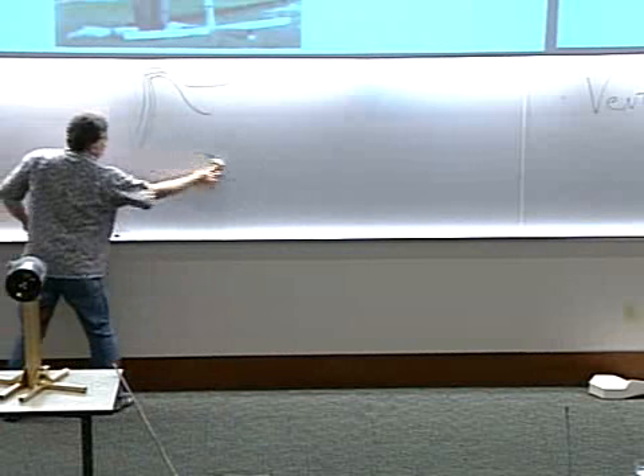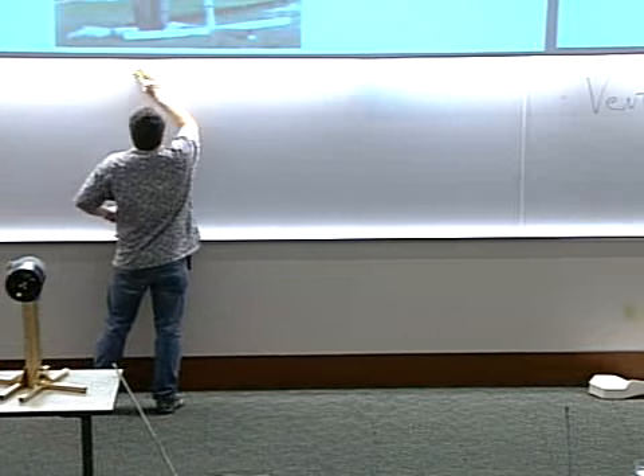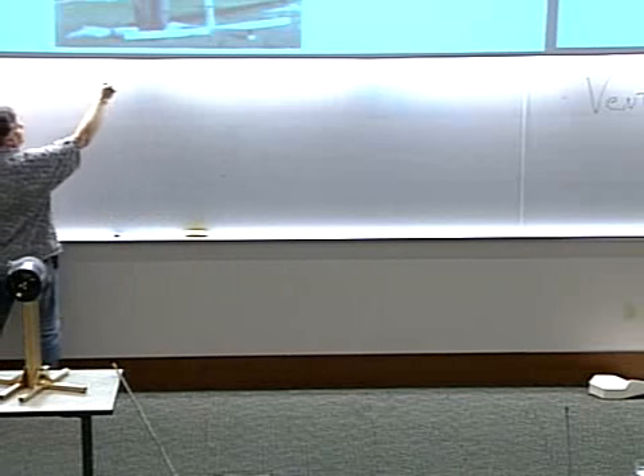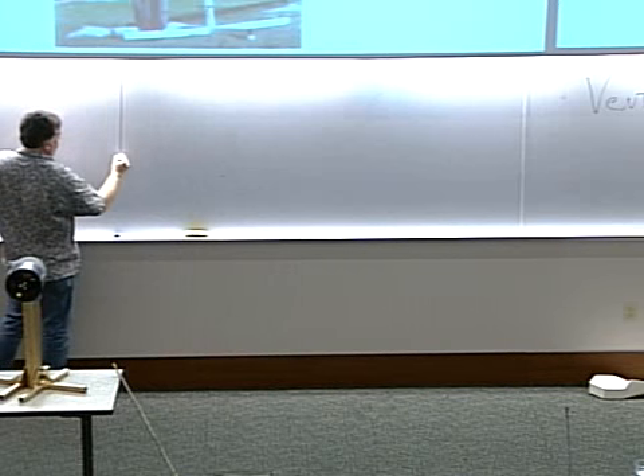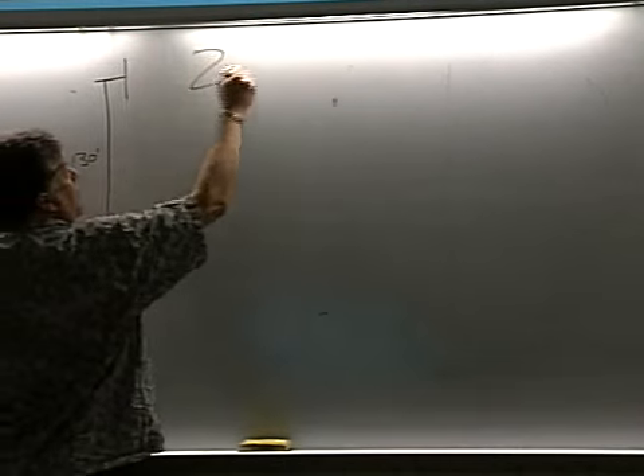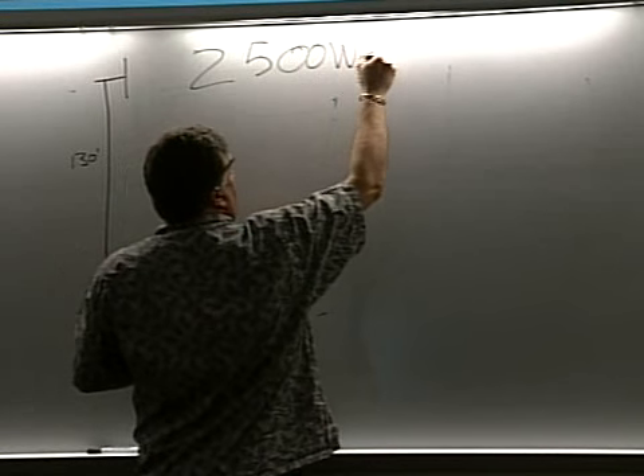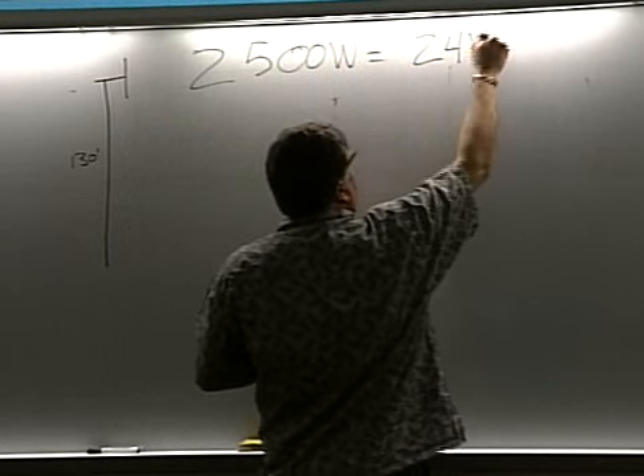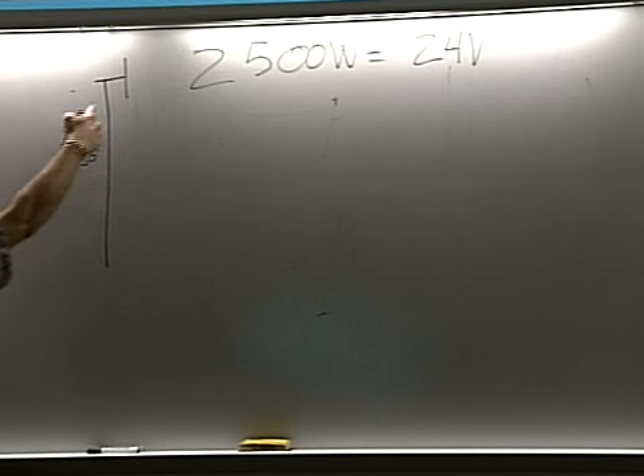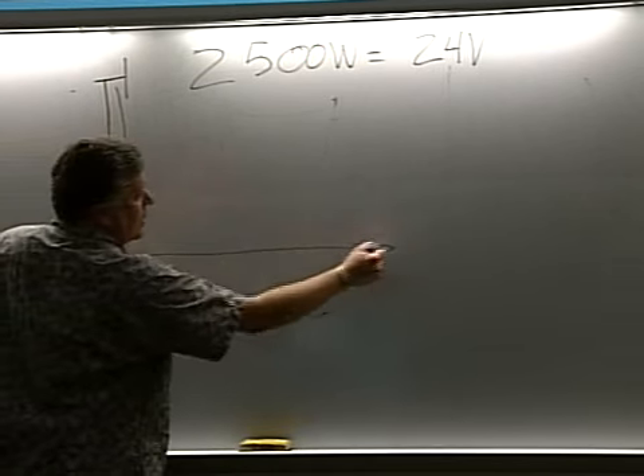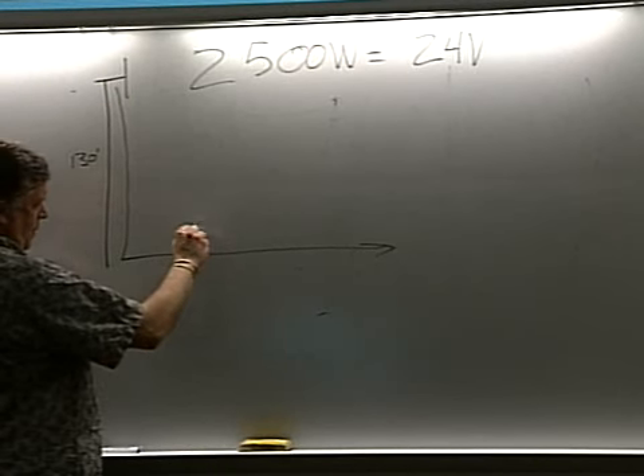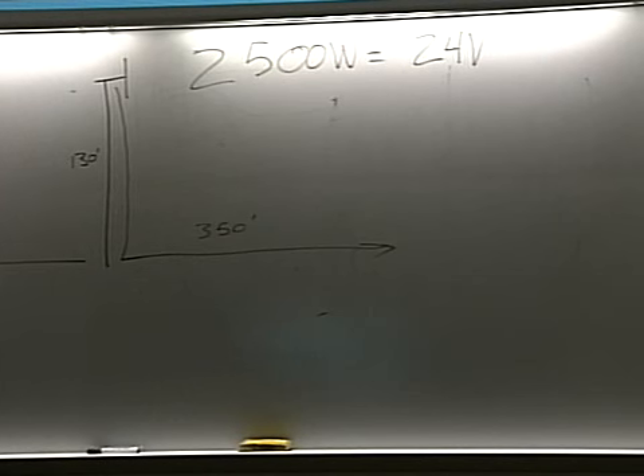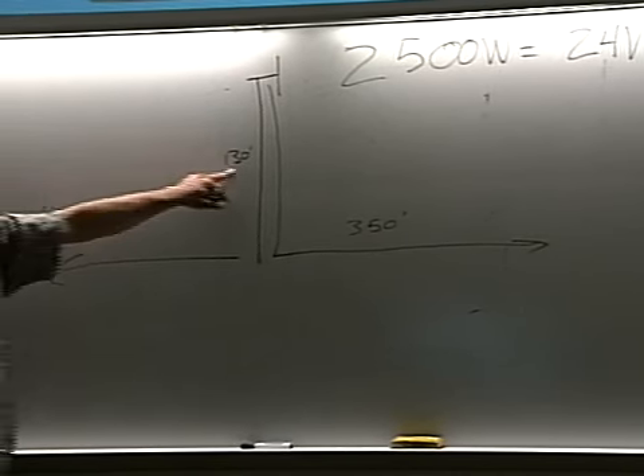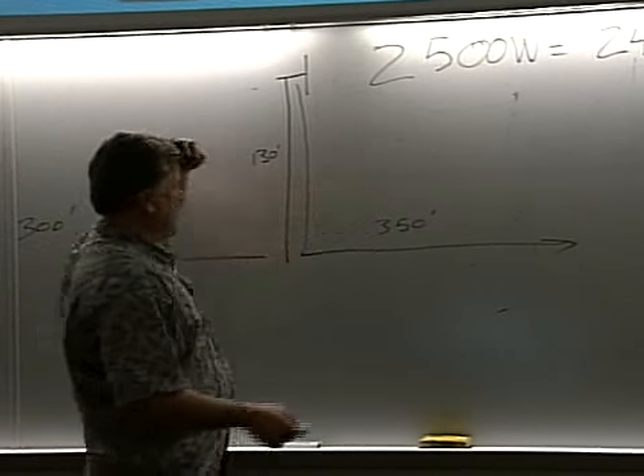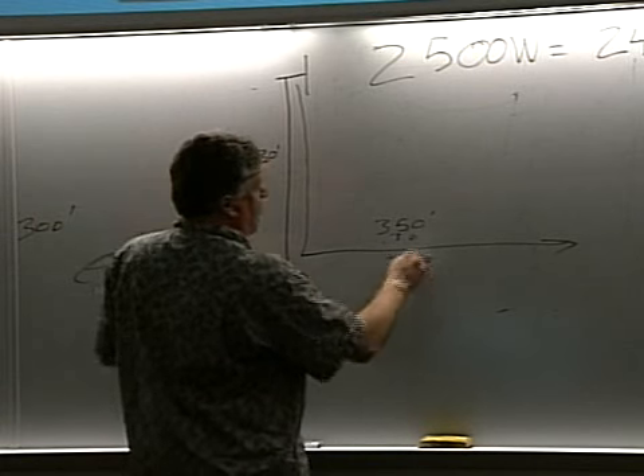In my backyard is a 2.5 kilowatt Proven, and what we have going on is a wind machine on a 130-foot tower. It produces 2,500 watts max and runs at 24 volts, three-phase wild AC. We're coming down with the conductors 130 feet, and then going horizontally in one direction, feeding one 24-volt battery pack, 350 feet. Now we're going another direction, 300 feet. So we have 130 feet plus 350 feet, let's call that 500 feet.